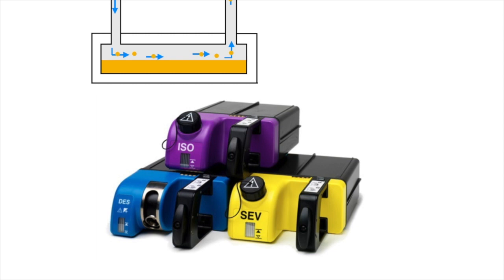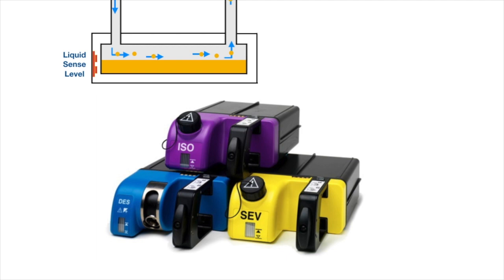This portion also houses the contact for the electronic temperature sensor and the liquid anesthetic agent level. There are four copper-colored circles that can be seen on the top surface of the front of the cassette. Information from the liquid level sensor is transmitted by this electronic bus to the anesthesia workstation. The cassette features accurate overfill protection, and the level sensing is electronic and more accurate than only visual sensing.